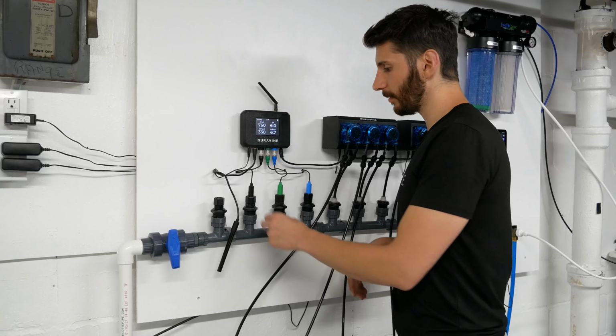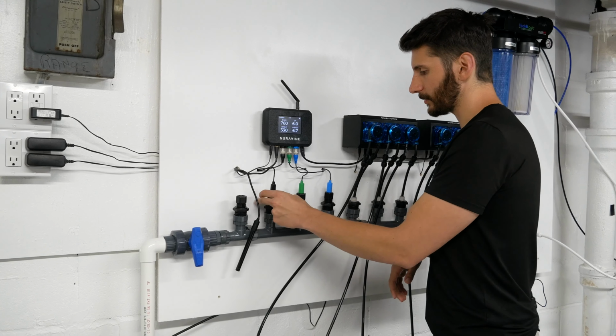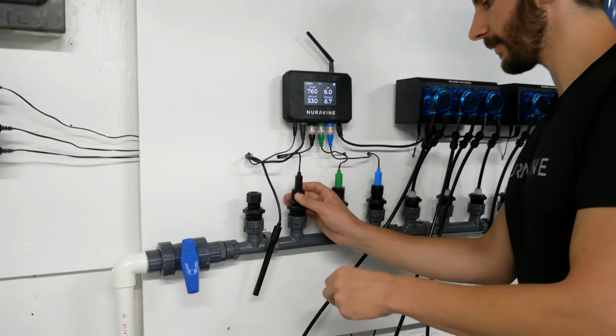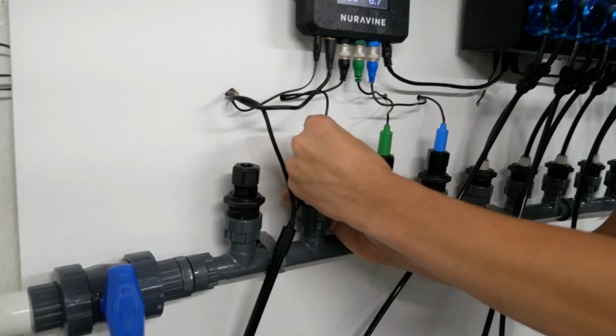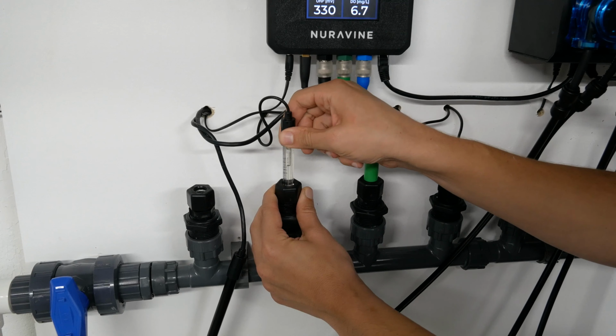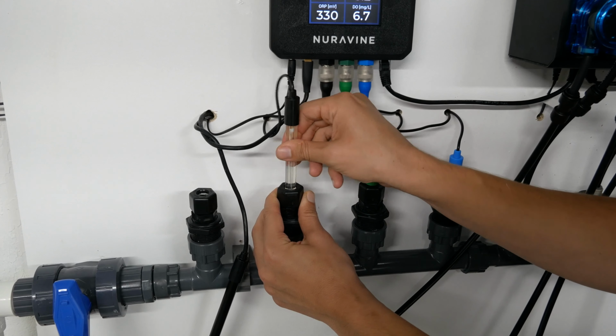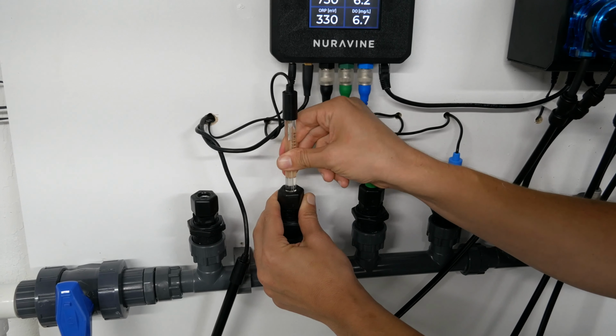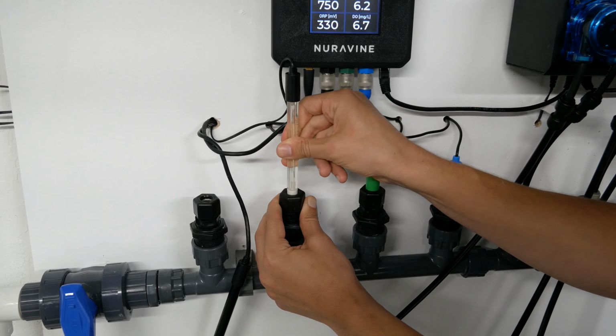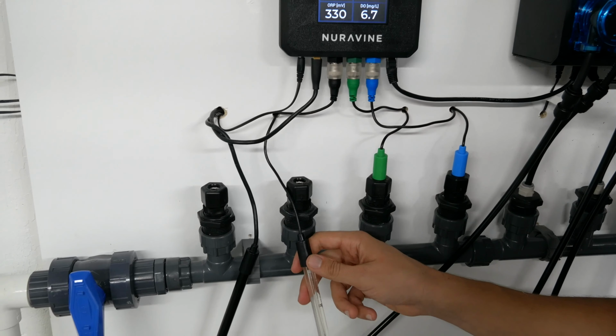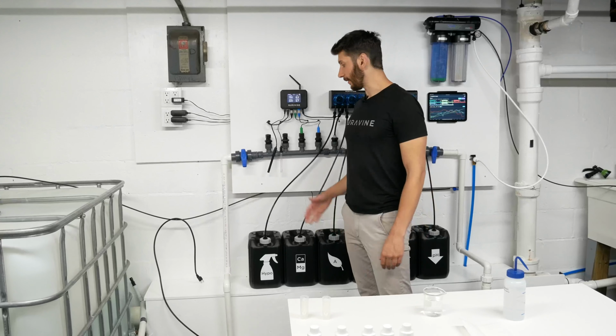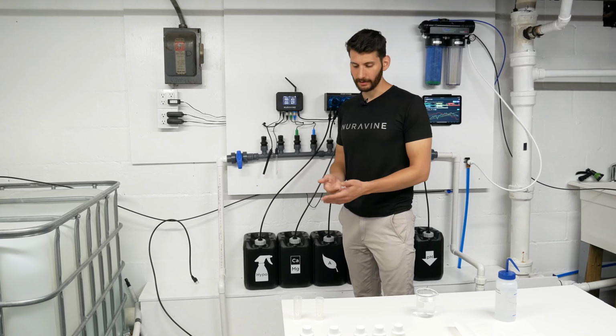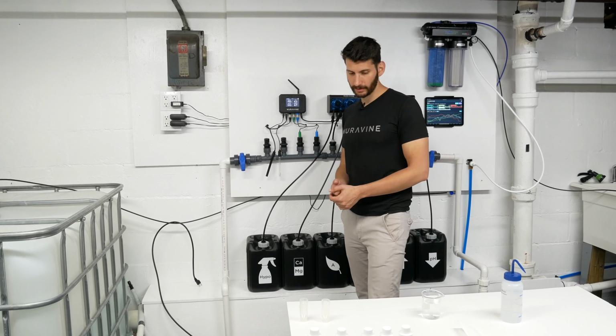Similar to the EC probe, I'm going to take the pH probe out by twisting this top nut right here, and then I'm going to twist the probe. So you're just going to give it a little twist and pulling motion at the same time, and sometimes it's a little tricky at the end, but keep at it, and once you get it out, you're good to go. Now we've got both of the probes out, we're going to fill up our bottles with calibration solution.